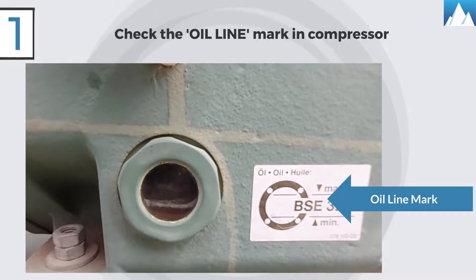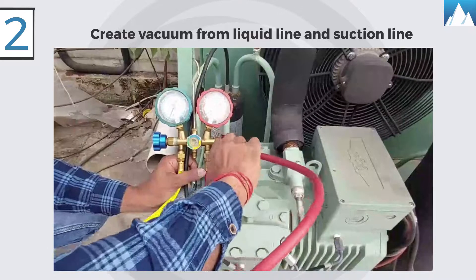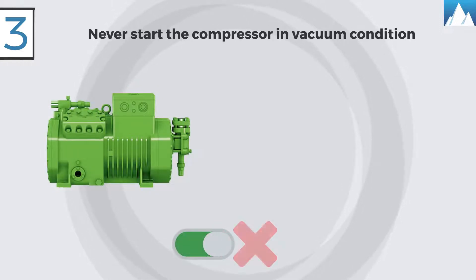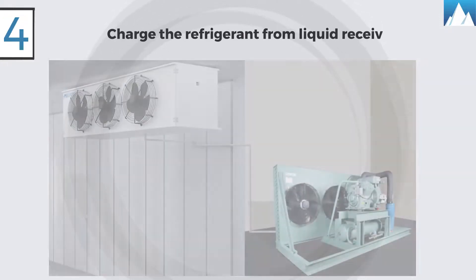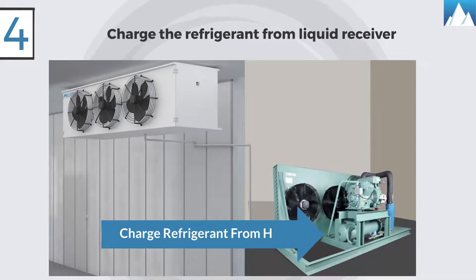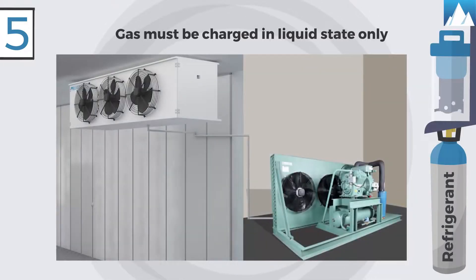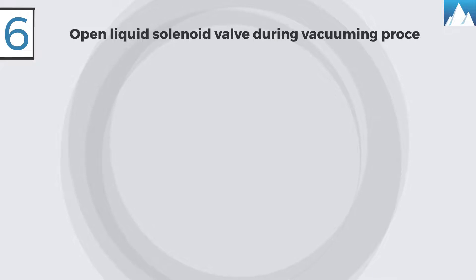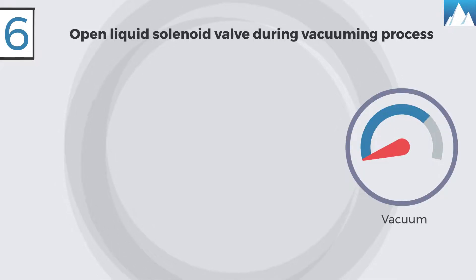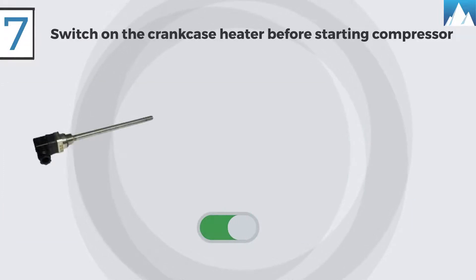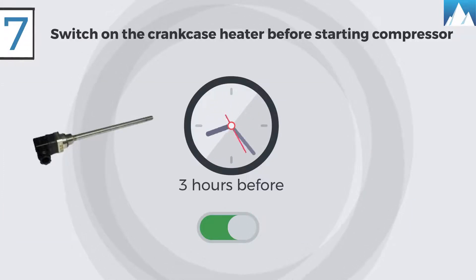Refrigerant charging method: One, the compressor is supplied with oil — check the oil level mark in the compressor. Two, create the vacuum from both liquid line and suction line. Three, never start the compressor in vacuum conditions. Four, always charge the refrigerant from the liquid receiver in the condensing unit. Five, gas must be charged into the system in liquid state only. Six, during the process of vacuuming the system and gas charging, open the liquid solenoid valve.